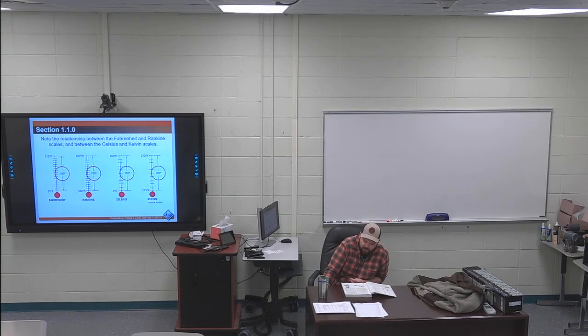Bimetallic thermometers. Second paragraph in 121 is an online test question. To calibrate a bimetallic thermometer, immerse it in a cold water bath that has a known temperature. Once the temperature measured by the thermometer reaches the known temperature of the bath, adjust the pointer on the thermometer's scale to match.